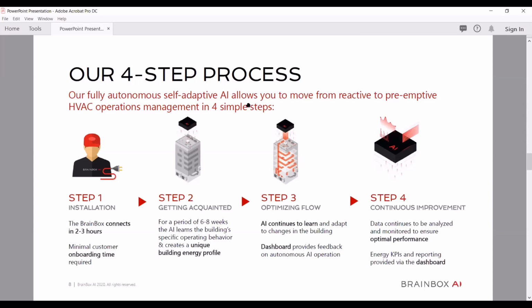At that point, after the 6 to 8 week learning period, we shift into autonomous mode, and that's when the AI is making regular decisions. We download data from the HVAC system every 5 minutes, and every 5 minutes we're providing a new set of instructions, optimal settings. The AI is recalculating what each zone and the building as a whole will face in the next 2, 3, 4, 5 hours, deciding whether modifications need to be made to the individual components of the HVAC system. That's what we call the autonomous mode.